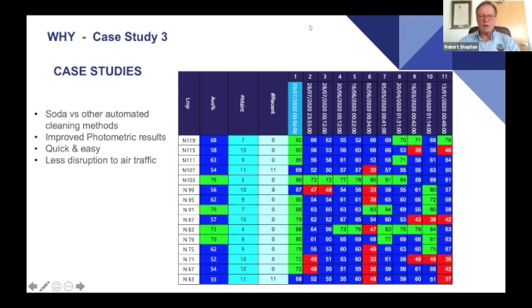It's in fact to provide safe operation. And I know that in certain regulators, and I can speak for the UK CAA, the inspectors will look at the test results over a period to see that these are being consistently achieved. So in fact, if you can at all do this, what you should do is do the photometric test and then the cleaning afterwards, based on the results, because what you had before is what the pilots are getting as a lighting service.